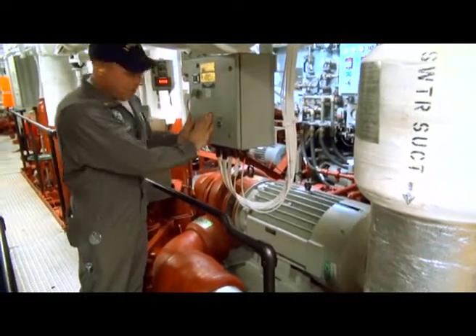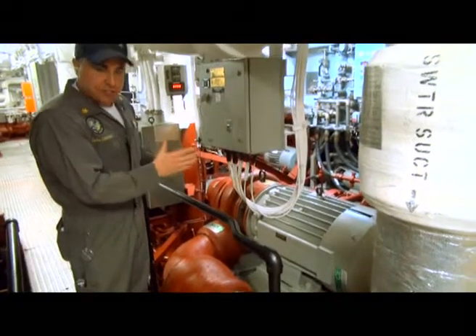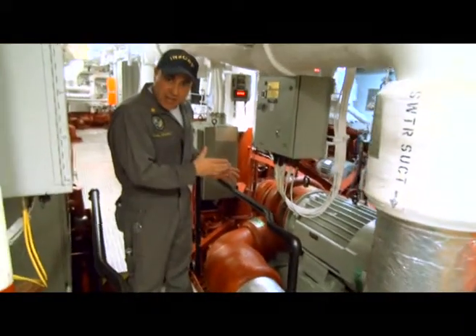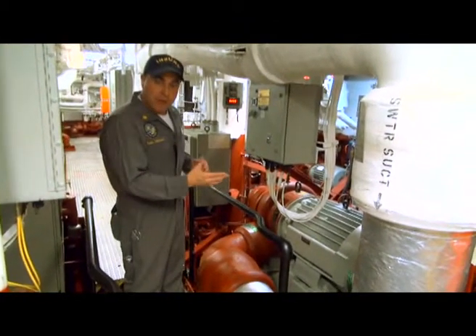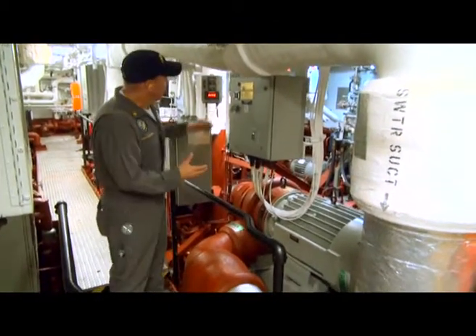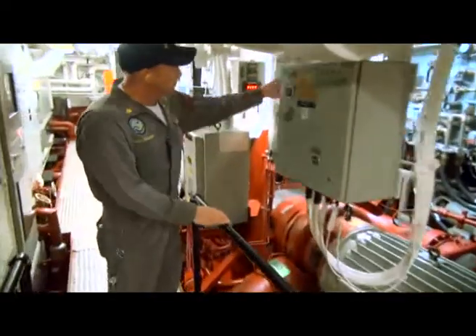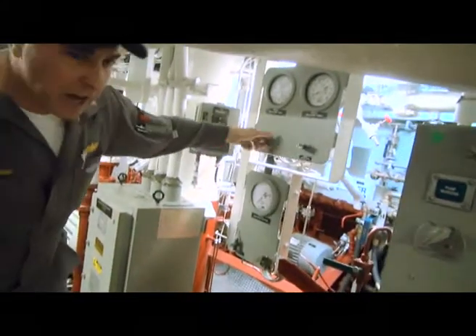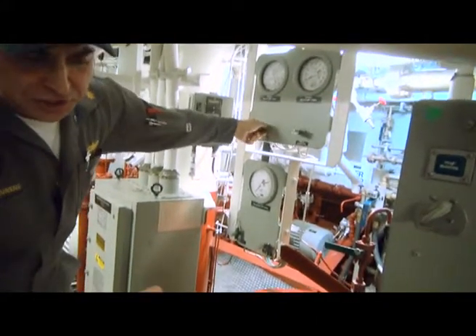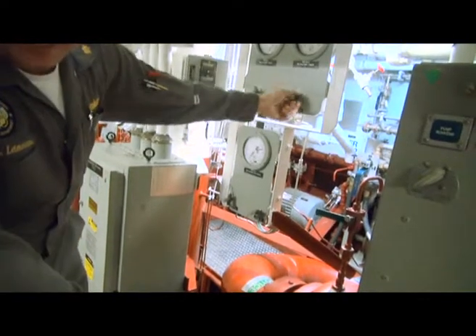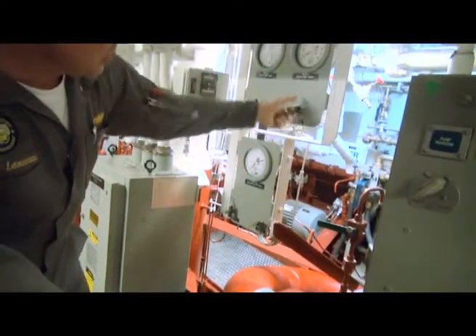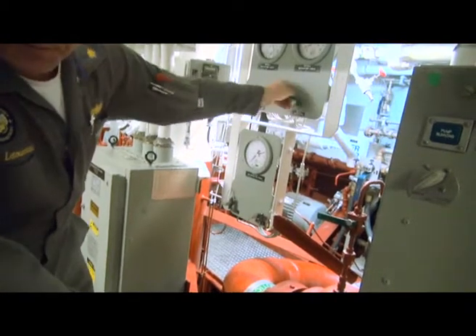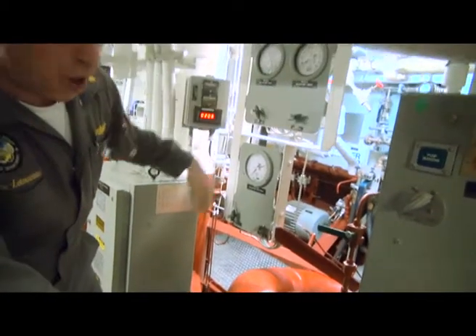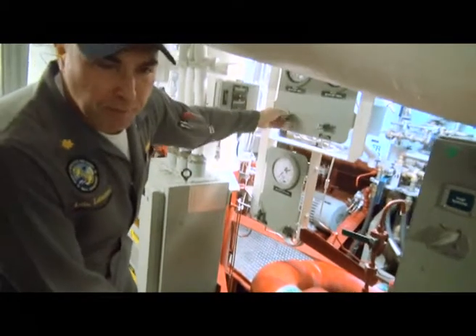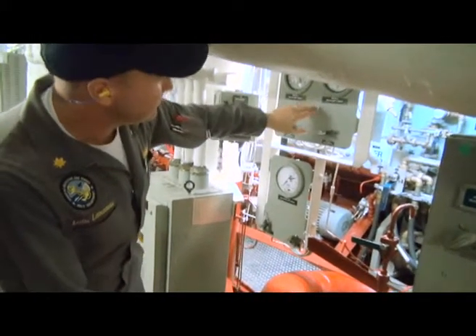So once we start this pump, like I said, suction pressure, discharge pressure, we're going to check the gauges themselves and check the proper operating pressures. With the gauges, we like to check the isolation valves, these hoop valves, make sure they're not seized. And a lot of seawater systems, especially auxiliary seawater systems, don't get a lot of love, so these get seized real easily. Some of the best maintenance you can do is just operate them from time to time. Just partially closed, partially open, keep them loose, keep them lubricated.